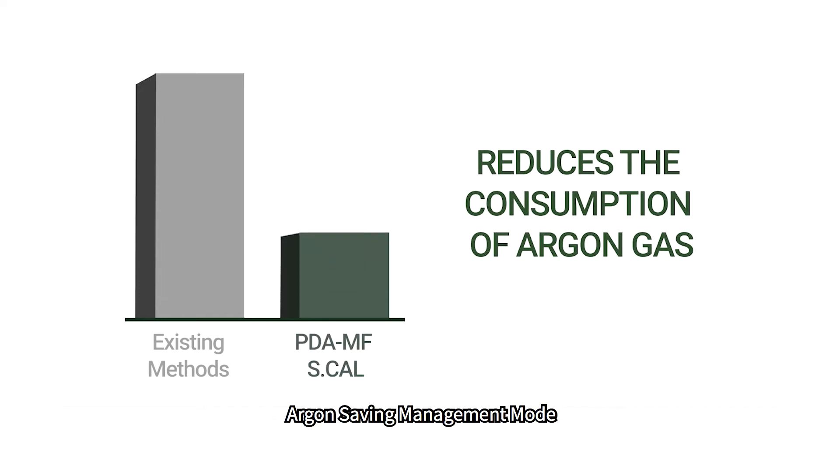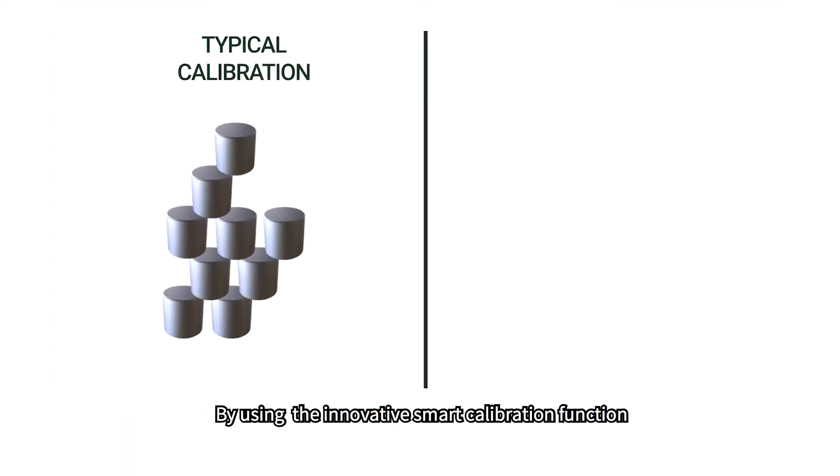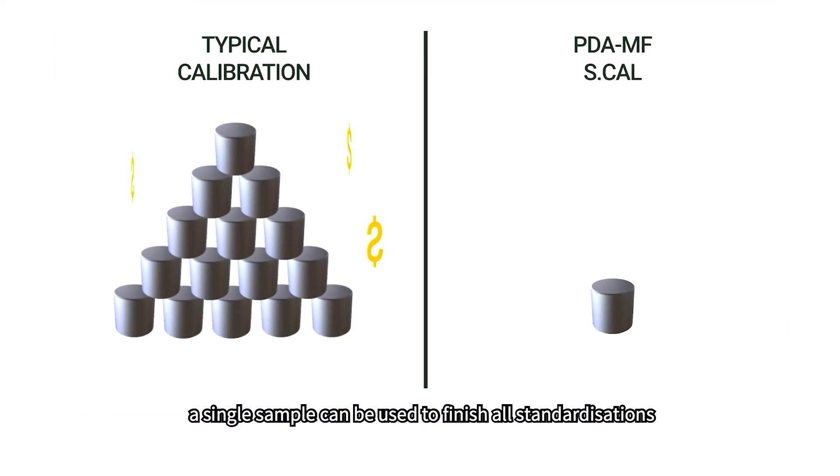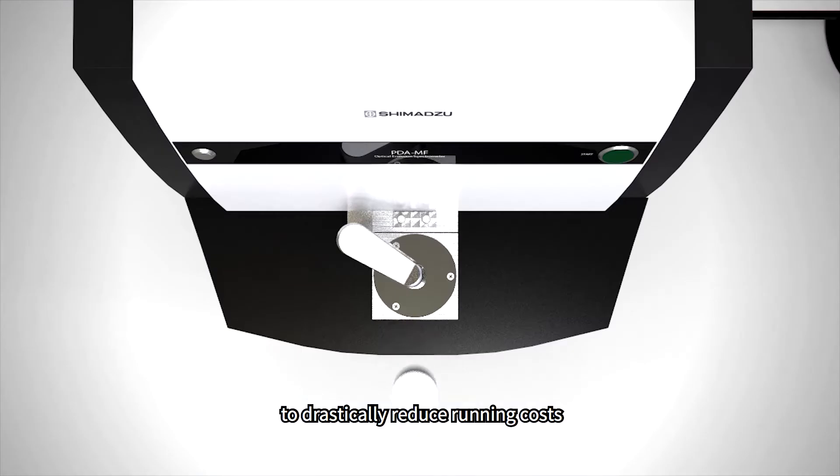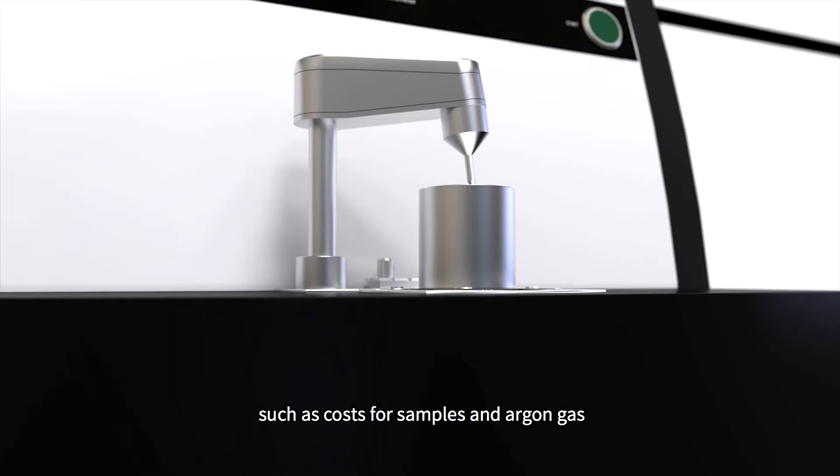With the new computer controlled argon saving management mode, the instrument can switch automatically between the analysis, standby and idle states to reduce the consumption of argon gas to a minimum. By using the innovative smart calibration function, a single sample can be used to finish all standardizations to drastically reduce running costs, such as costs for samples and argon gas.